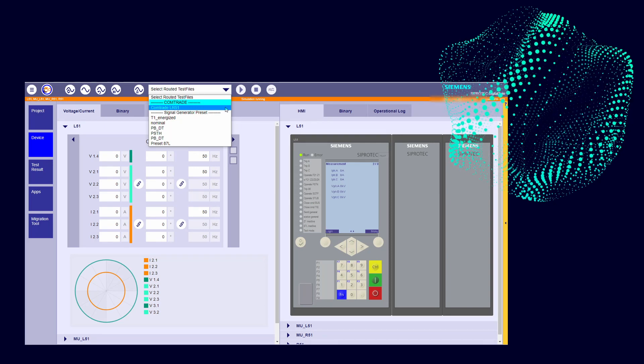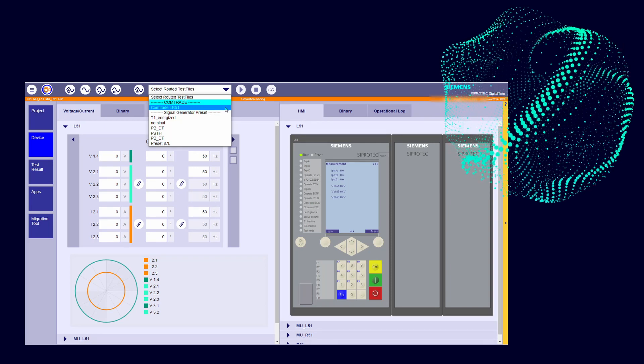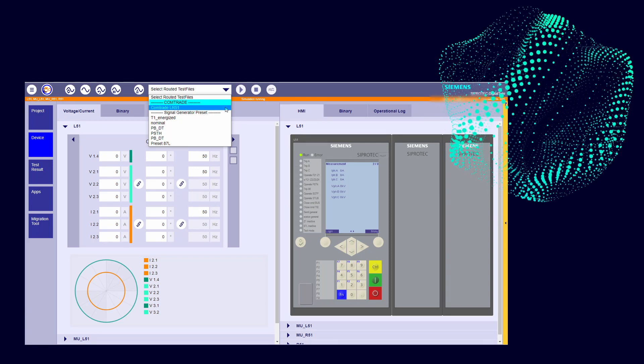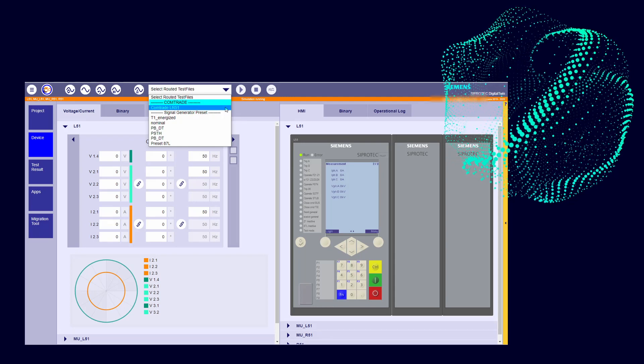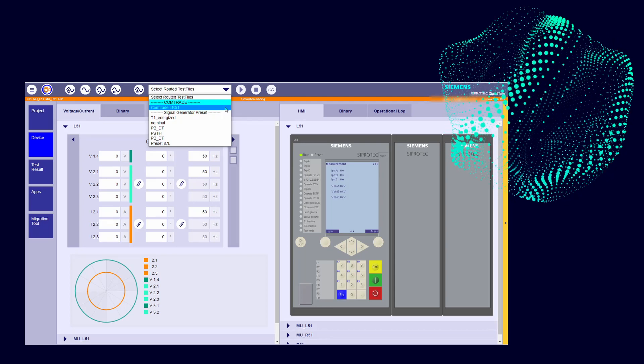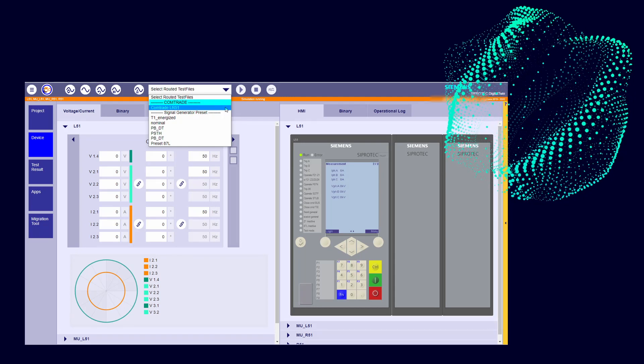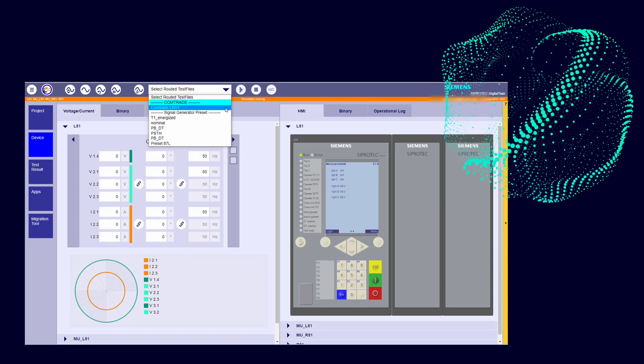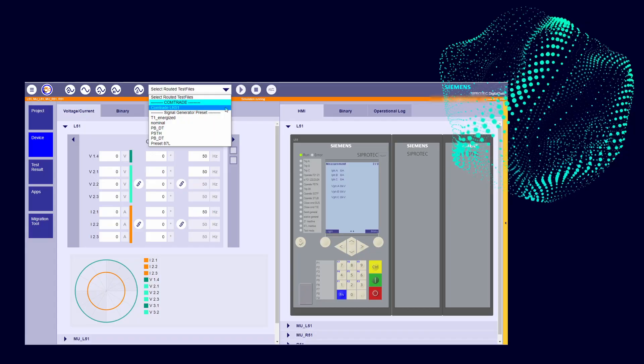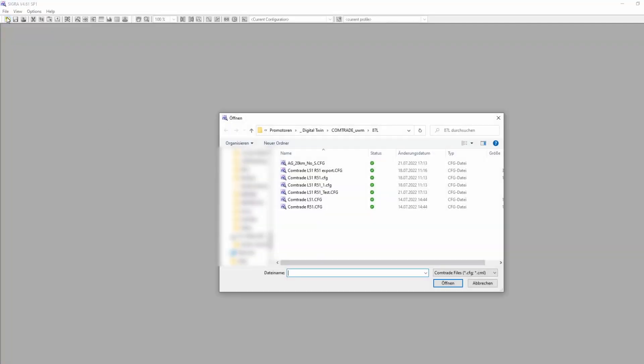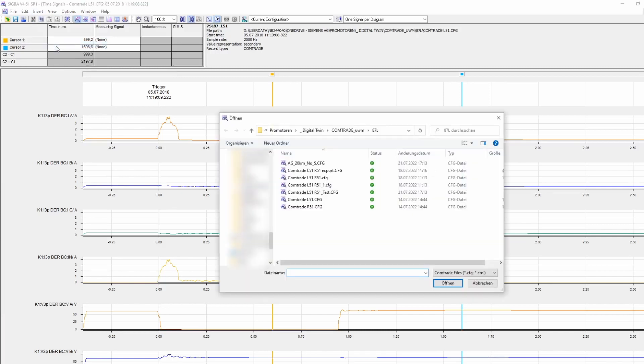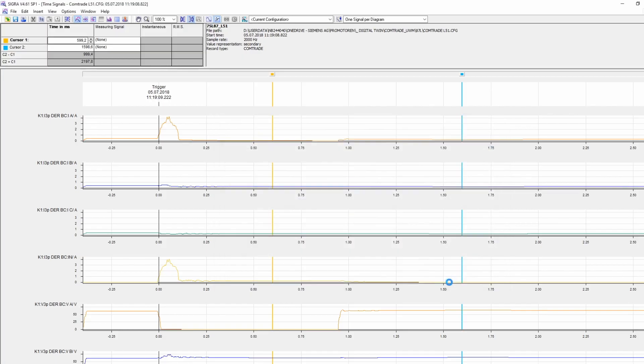If you don't have a combined COMTRADE, for instance, if you got from the field independent files for each end, you can merge both files in one using our DIGSI software. I will show you how: start DIGSI and open the first COMTRADE. Let's say in this case, the one from the left side, and then insert a new record selecting the file from the right end. In such a way, we have both COMTRADE in the same file right now.